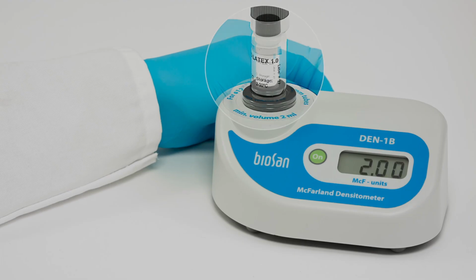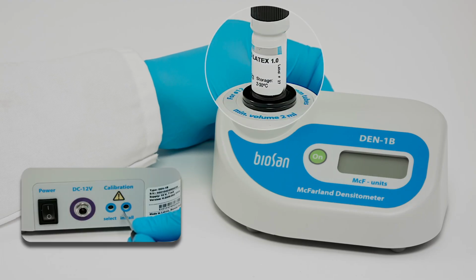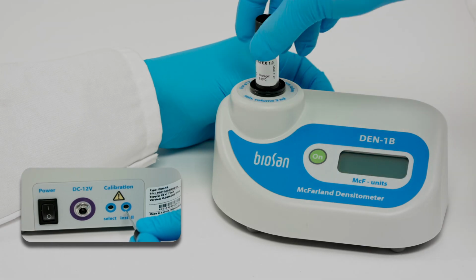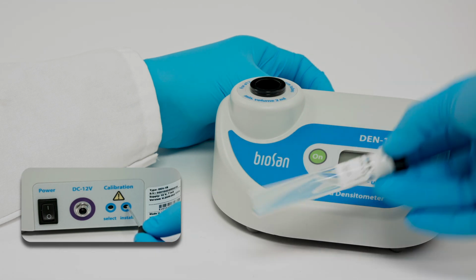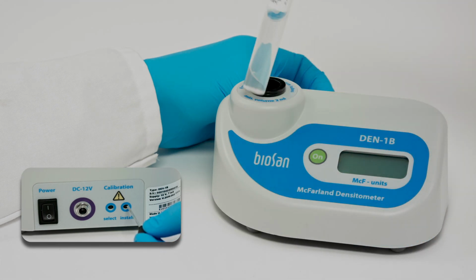If the inserted standard has a lower turbidity value than the previous standard, the Install button will not save the value. If you are using the correct standard, then gently shake it or replace the standard.